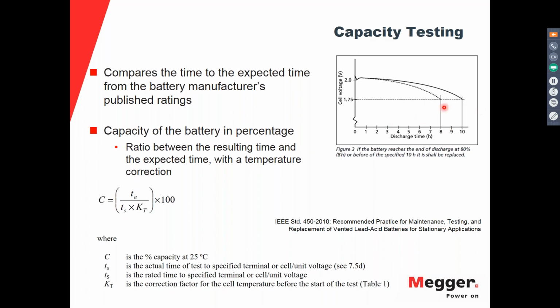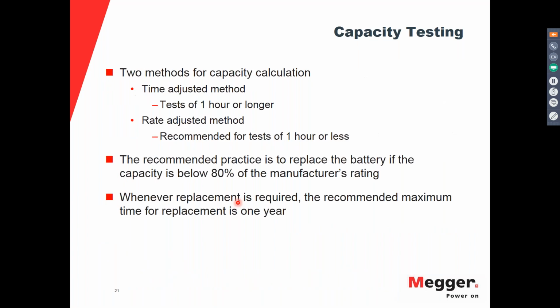And here we can see, for example, a battery in a new condition should last for 10 hours. And then during this test, it lasted for 8. That means that the battery has 80% of capacity. That's the basic concept about the capacity calculation. It's a ratio between the actual time and the expected time with a temperature correction. Now, this is one of the methods to calculate the capacity, and it's called the time-adjusted method. The formula that I just showed is that one.